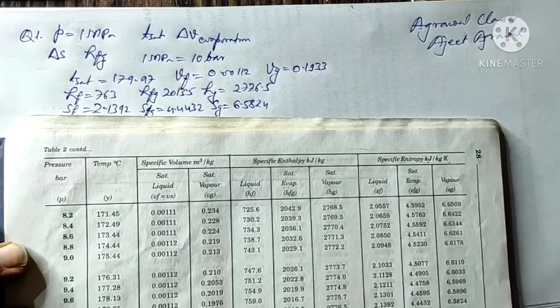Now we have to find the saturation temperature. The saturation temperature corresponding to 1 megapascal, or 10 bar, is equal to 179.97 degrees Celsius. It is written in the steam table. Then the change in volume during the evaporation. Before evaporation the volume was 0.00112 meter cube per kg, and after evaporation the volume is 0.1933. So the change in volume during the evaporation, Vfg equals Vg minus Vf. We substitute the values: 0.1933 minus 0.00112. This comes out to be 0.19218 meter cube per kg. The unit is again written in the steam table.